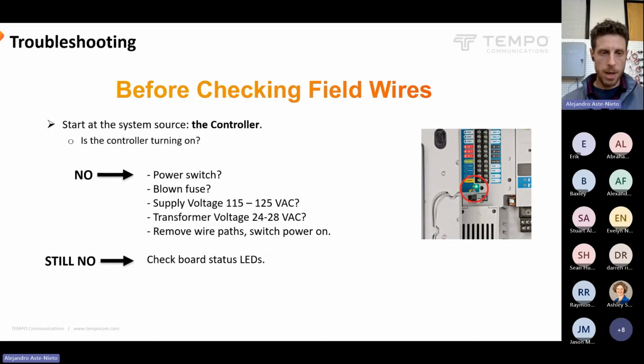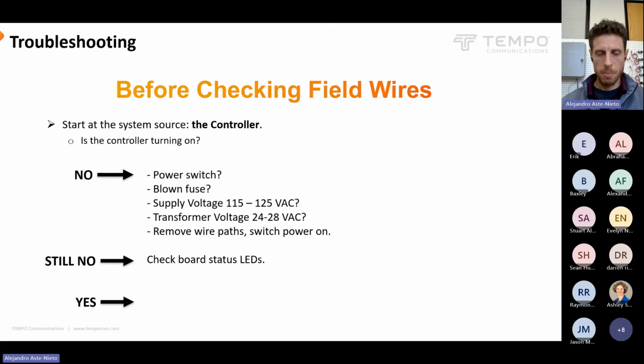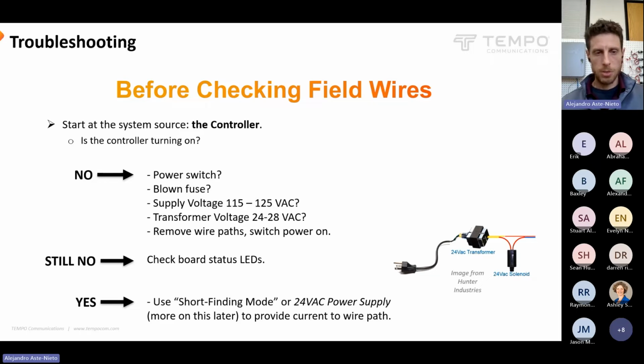However, if we remove some wire paths and the controller now turns on for the first time, that indicates there was an overcurrent that the controller refused to operate with in order to protect itself. So that means we probably want to take some measurements with our clamp meter, and in order to do that, we need a source of power. If the controller refuses to turn on and give us that power, ideally it will have a short finding mode or a wire test mode like some of the newer and more sophisticated systems have. Otherwise, if the controller can't really help us, we can build our own power supply, and we'll talk about that.